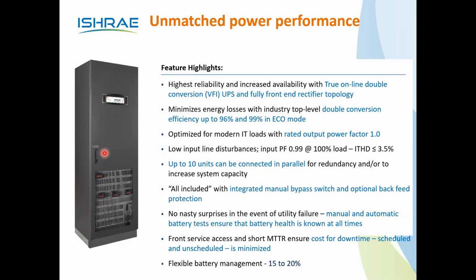Overall, if you consider the commercial offer, 35 to 40% is the battery cost only. With this flexible battery management concept, huge money can be saved on OPEX, operational expenses. Actually, the battery life can be more than 5 years. With this topology, the battery can be replaced only one time in the lifetime of the UPS system, say 10 years. Otherwise, it needs to be replaced 3 times. So this flexible battery management is available in all the technologies. Need to specify about this.